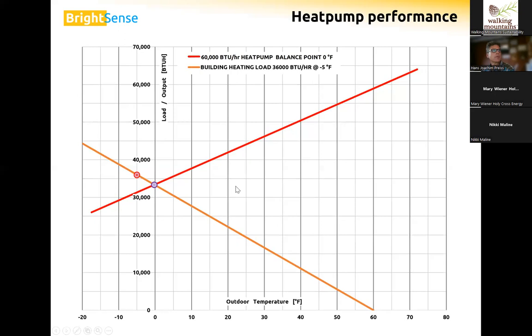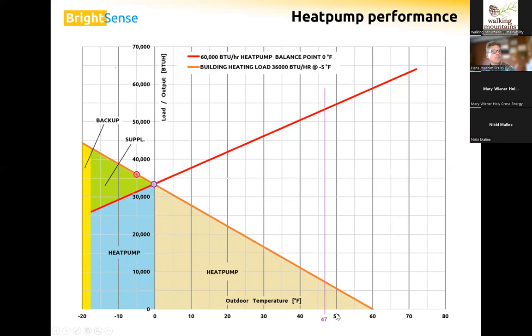and moving forward, some more illustration of what this means in terms of efficiency. So here we have our balance point again at 0 degrees. That's how far down the temperature scale this heat pump would be able to heat this home on its own. And so this beige area here represents the energy that the heat pump would be able to deliver. When it gets below the balance point, the heat pump would still be able to deliver what's shown in blue here, but we need some supplemental heat from this green. That's our supplemental heat that we need to source elsewhere. We'll be talking about that in a minute.